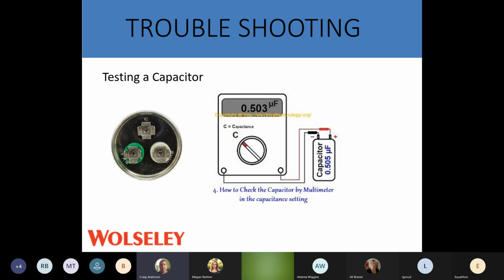People would come in and they would just grab one because they thought that was a problem. The fan didn't come on, but they never tested it. Takes 5 minutes, test it, make sure you got the right microfarads, and move on to the next step. So testing, using your testers, the proper equipment, the proper tools helps tremendously when you're out there doing some troubleshooting.